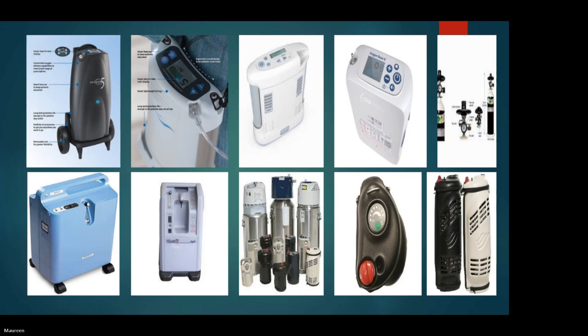Now, I'm going to say a wee bit about pulsed flow oxygen. It is not the same as continual flow oxygen, all right? You have to activate a pulsed flow device by breathing in through your nose. If you don't breathe in through your nose, you won't activate it and you won't get your oxygen delivered, okay? And on a pulsed flow, you cannot use a mask. Okay, it doesn't work. However, the SeQual Eclipse can also do continual flow up to 3 litres per minute of oxygen. That's the maximum you can give through it.